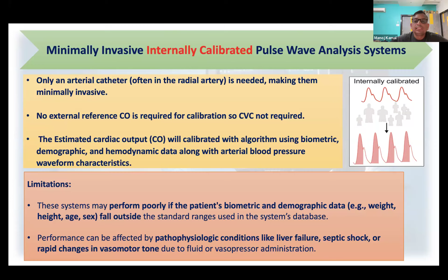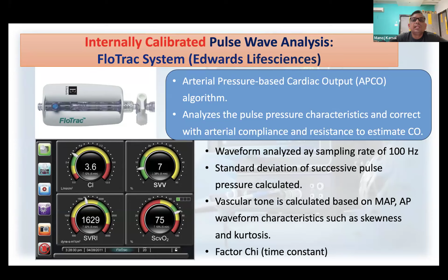An internally calibrated pulse wave analysis system is FloTrac. It uses an arterial pressure-based cardiac output algorithm. It analyzes the pressure characteristics and corrects for arterial compliance and resistance to estimate the cardiac output. It analyzes at a sampling rate of 100 Hertz, and the standard deviation of successive pulse pressure is calculated. Vascular tone is calculated based on the mean arterial pressure and arterial pressure waveform characteristics such as skewness and kurtosis, and it also requires the factor chi as a time constant for the calibration of the calculation of the cardiac output.